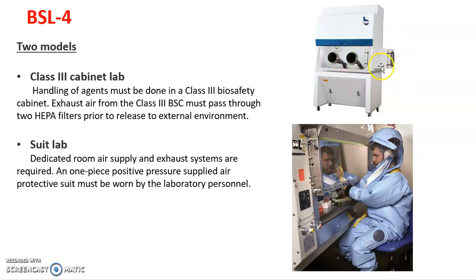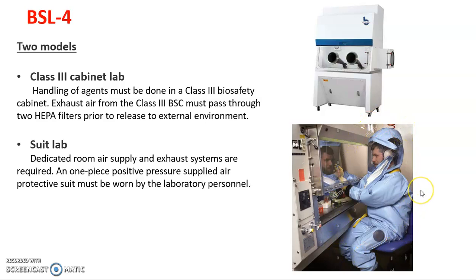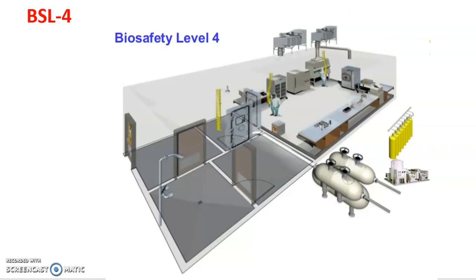In the Class III cabinet model, all work is done inside a very closed biosafety Class III cabinet with a small autoclave or decontaminator. Everything entering the cabinet is decontaminated, and everything taken out is also decontaminated before being released into the laboratory. The person working with the pathogenic microorganisms is not in direct contact with them. In the suit lab model, the person wears a positively pressured suit that pushes away microorganisms and does not allow them to enter the suit or reach the person.